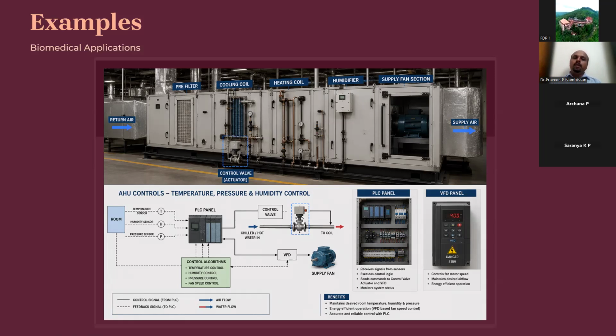Why are we doing all these things? This will be monitored in the BMS system, the building management system. In that building management system, we have a graph. A zero line will be there, then high and very high lines, low and very low lines. So if the temperature crosses high, it will give us an alarm. At the same time, I have to go and check whether the system is perfect, whether the sensor is perfect or not. If the sensor is faulty, I have to replace it. Otherwise, I have to inform the respective section to stop the manufacturing.